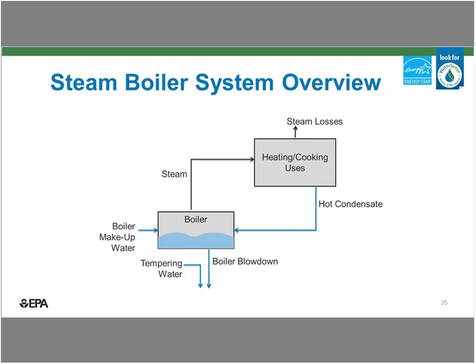So this is a very simple boiler sketch to orient everyone again. Steam is produced in the boiler and used for space heating or potentially other uses. Once the steam gives up its heat, it condenses back to water and is often collected and returned to the boiler. This is the hot condensate. Similar to cooling towers, over time, minerals can build up in the boiler, and a periodic blowdown is required to remove them from the system. The blowdown is very hot, and frequently there's tempering water that is required to be mixed with the blowdown to help reduce the temperature below 140 degrees so that it is permitted to be discharged to the sewer. Makeup water is provided to make up for the steam losses and the boiler blowdown.